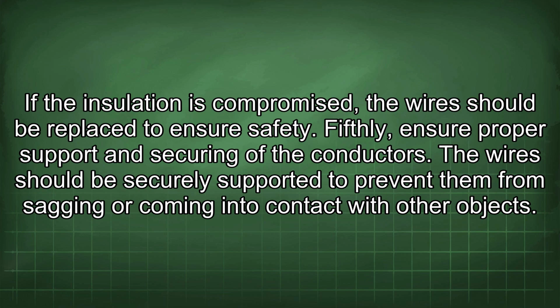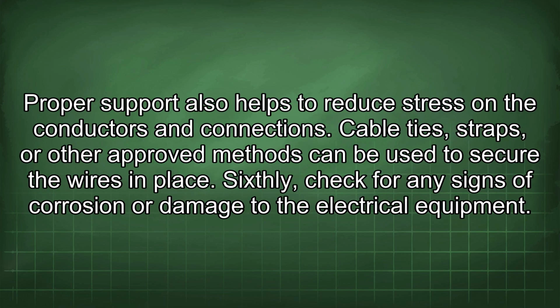Fifthly, ensure proper support and securing of the conductors. The wires should be securely supported to prevent them from sagging or coming into contact with other objects. Proper support also helps to reduce stress on the conductors and connections. Cable ties, straps, or other approved methods can be used to secure the wires in place.